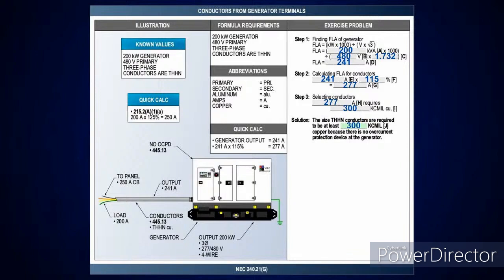Here's another one where I'm doing the conductors from the generator terminals. Okay. I've got a 241 output. We're telling you that's what it is. How do I know that? Well, I've got a 200 kVA generator here, and I've got 480 volts. It's 3-phase, 1.732. Okay. And it'll give me 831 volts. Divide all that in, that gives me 241 amps.